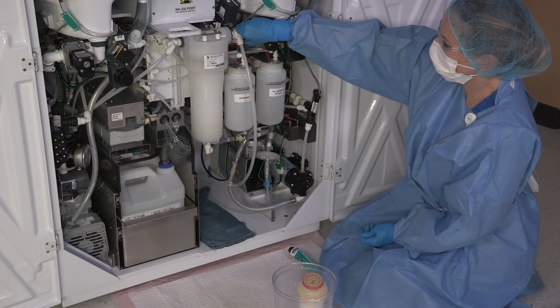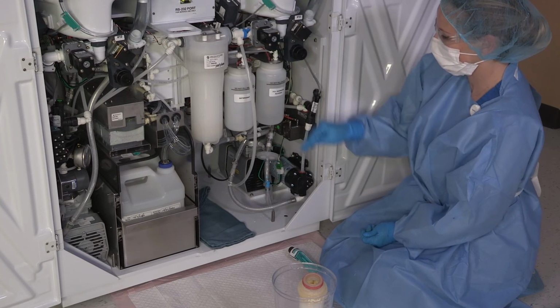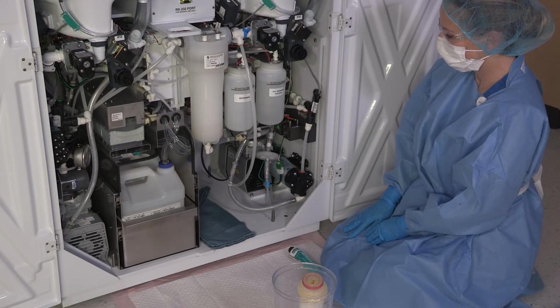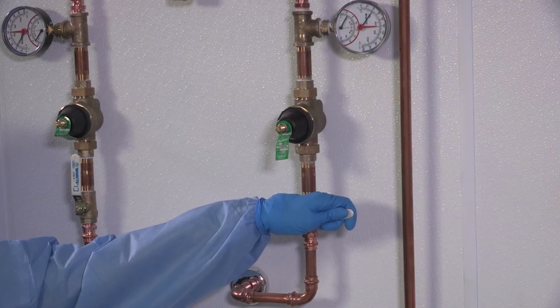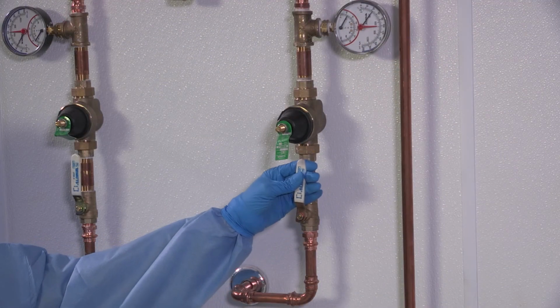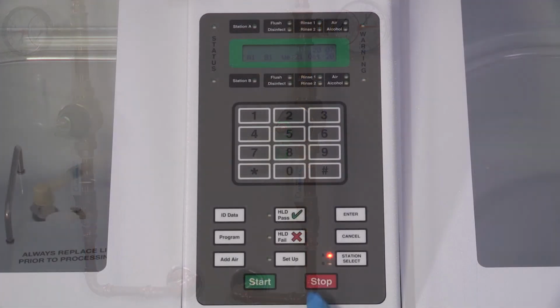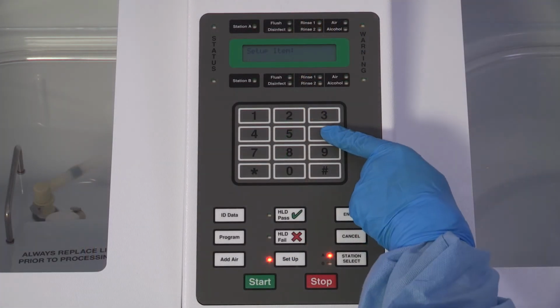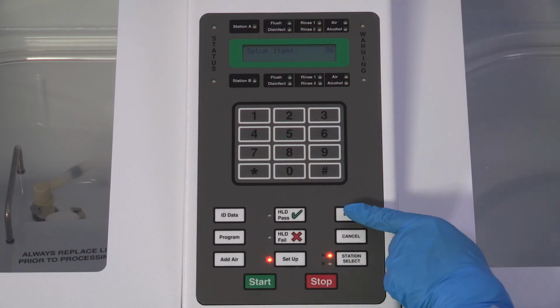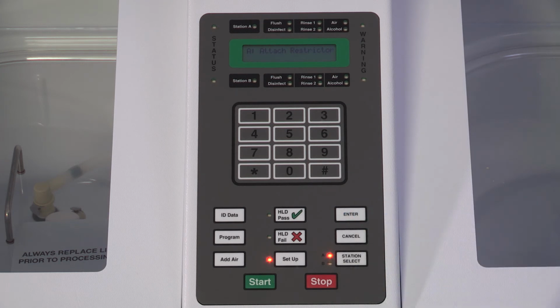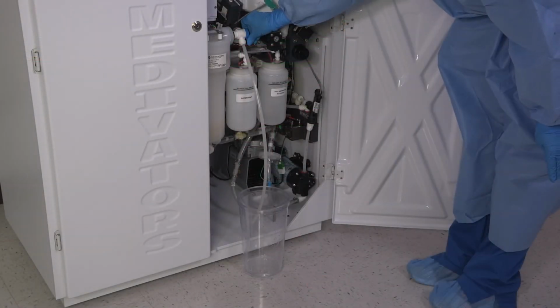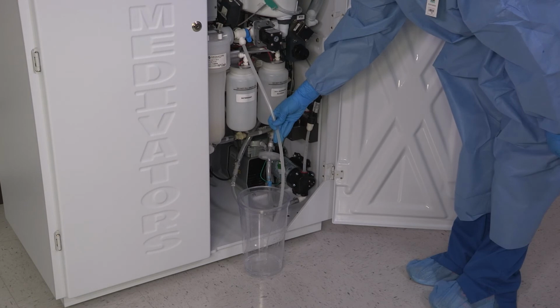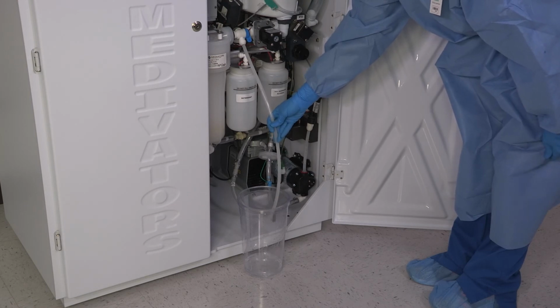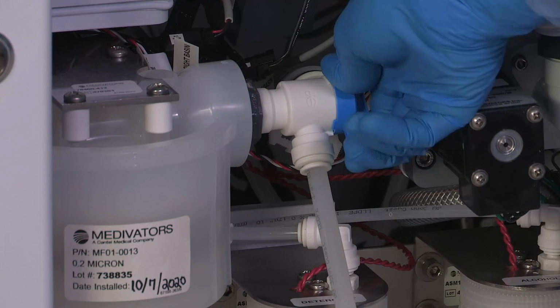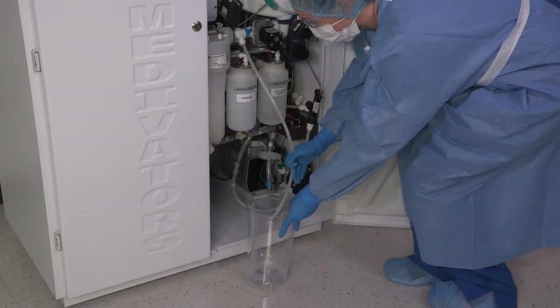Close the handle on the air bleed valve. Stop and take a moment to ensure this step is done. Slowly open the main water supply valve. Immediately after the 0.2 micron water filter is changed, you must complete these 2 steps. Purge air from the system by using the steps to release the pressure in the water lines, ensuring a steady stream of water is exiting from the air bleed purge line.